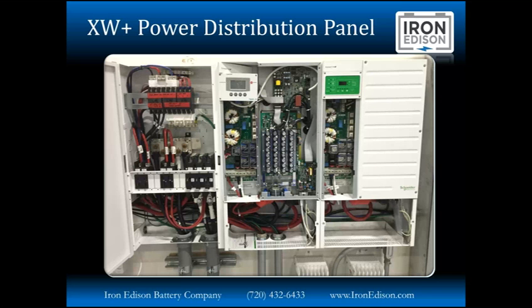covers that will cover up all the wires, providing a really safe and clean look at the end of the day. On the left-hand side of this power panel, on the top, labeled with the red tape, is the 3-phase AC input and output and bypass breakers. You can see there's a white plastic box at the top, and this is a special assembly made by Schneider Electric to take a single leg and split it up between the 3 different sets of breakers. On the bottom left-hand side of the power panel, you can see there's 2 sets of panel mount breakers for the charge controller inputs and outputs. And on the right-hand side of the power panel are the 3 250 amp DC disconnects for the 3 inverters that we used in this 3-phase application.